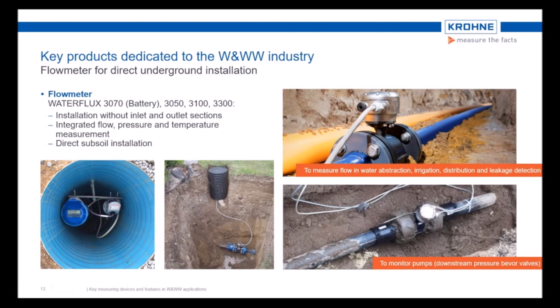In this case, the flow meter will be installed just beside the pumping station within the ground. You just need a smaller low-priced plastic chamber for the converter and maybe the GSM module. Of course, the meter is coming with a special subsoil coating and stainless steel connection box, which is fully potted and fully IP68, which means NEMA 6P.